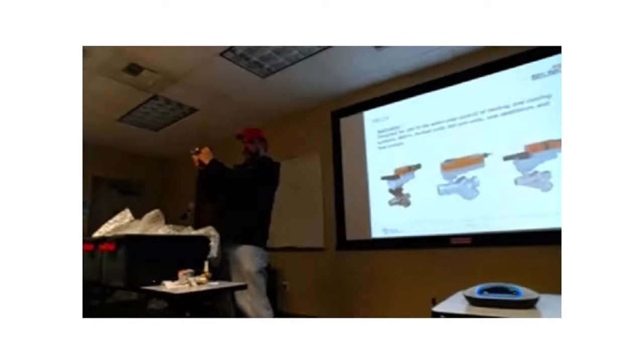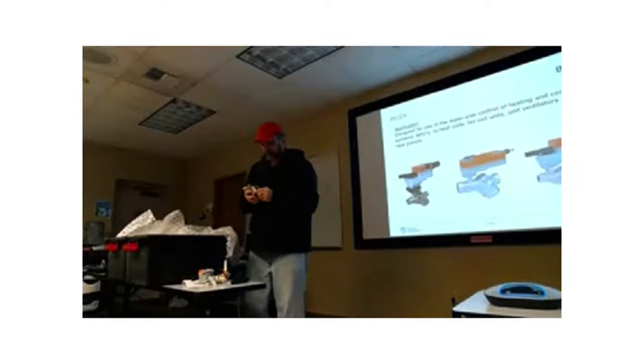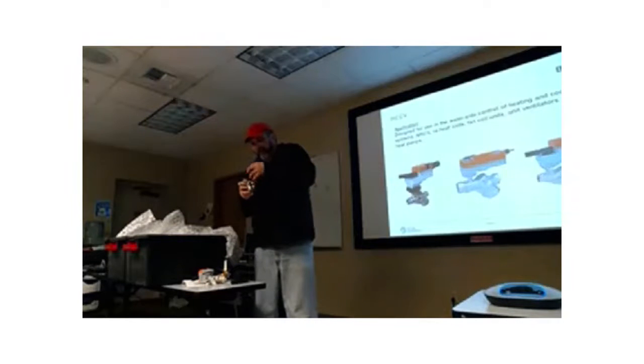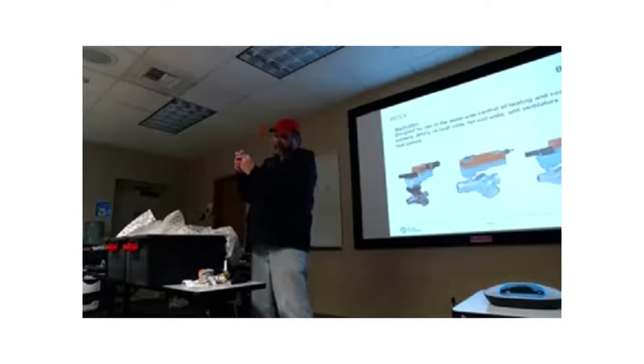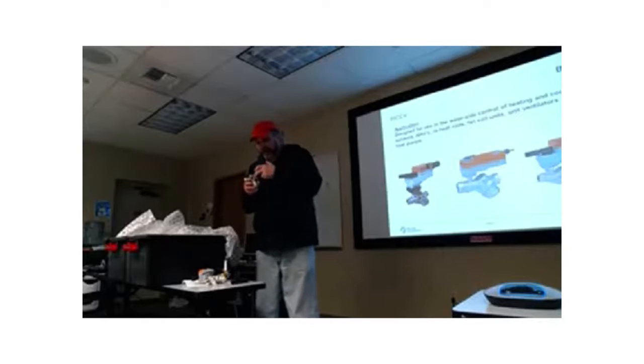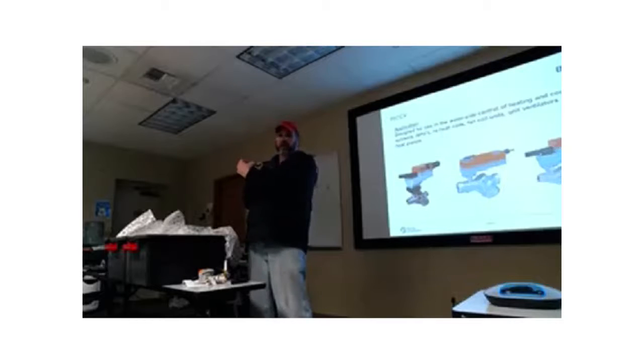This is actually a spring force balance mechanism. You have a plunger here with a spring and a shaft, and you have a diaphragm here in this chamber. The high side is on the top, the low side is on the bottom, the downstream side. The water goes through here. It tends to push this plunger down. The water goes through this valve. This is just a regular old CCV, like you guys know.